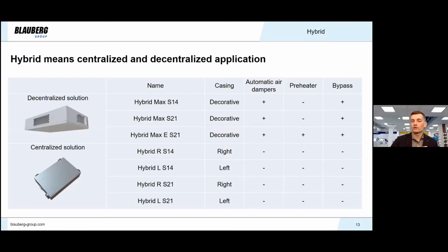At the bottom part of the table, you can see 4 units for centralized application. These are either with S14 or S21 control system and either left or right modification. The hybrid units for centralized applications are not equipped with air dampers because they are mostly not needed in this case. Bypass also is not needed because the power consumption is less than 30 watts for each fan, which is allowed by the Eco Design regulation.